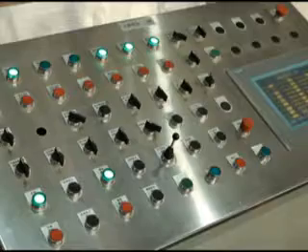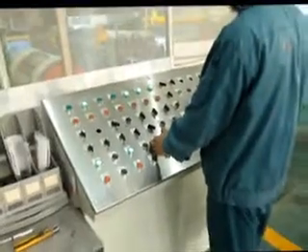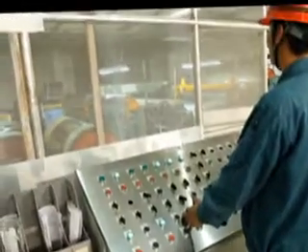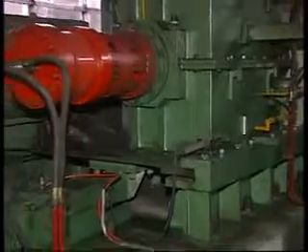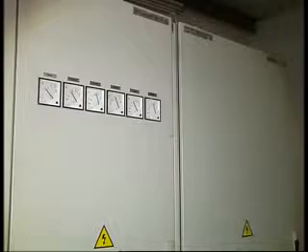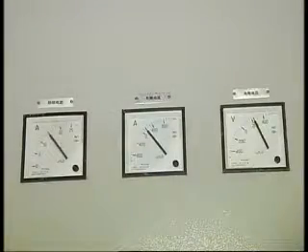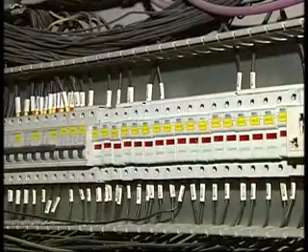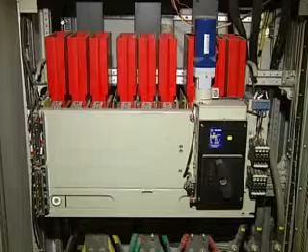The uncoiler and recoiler tension can be set and adjusted, and the whole line can be controlled from the main operation desk. The uncoiler, bridle rolls, and recoiler are driven by DC motors. The full-digital DC control system with high-performance speed and torque control functions can meet the requirements of quick response and control accuracy. Motors and power are collectively controlled by an AC motor control center with compact structure and reliable performance. The main control system adopts a PLC system which achieves digital calculation, parameter setting, and automatic logic control.